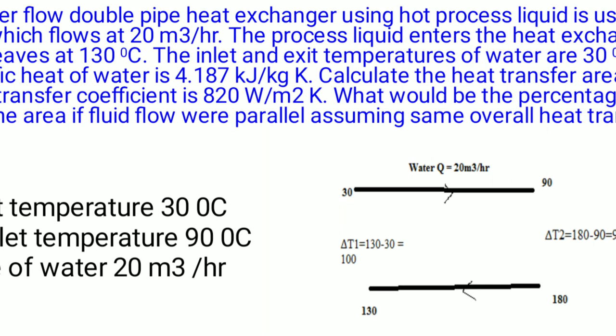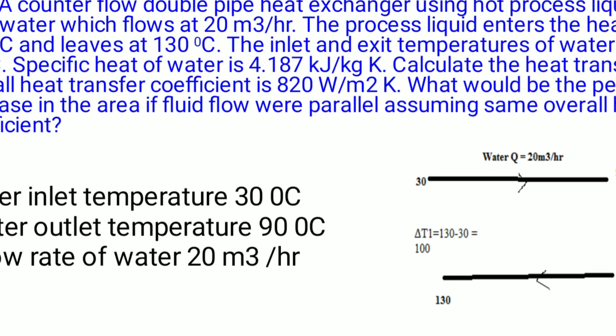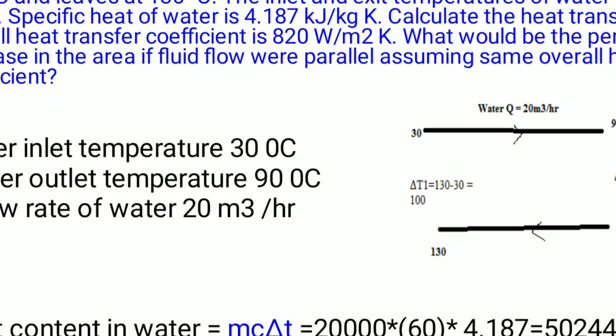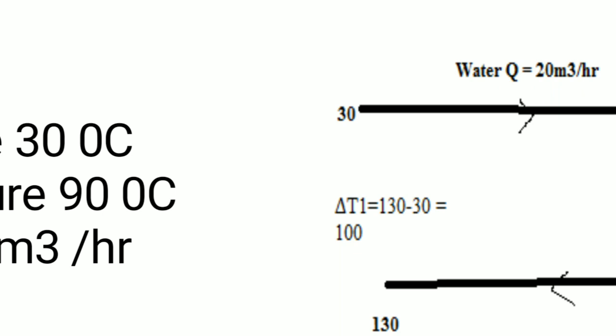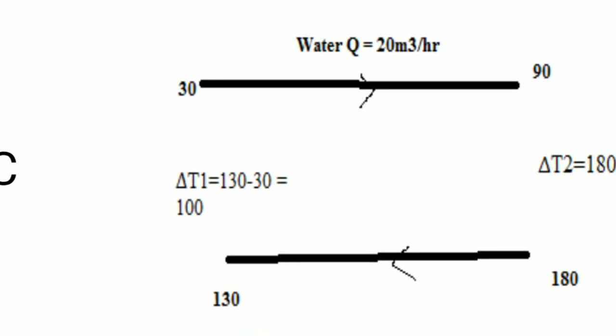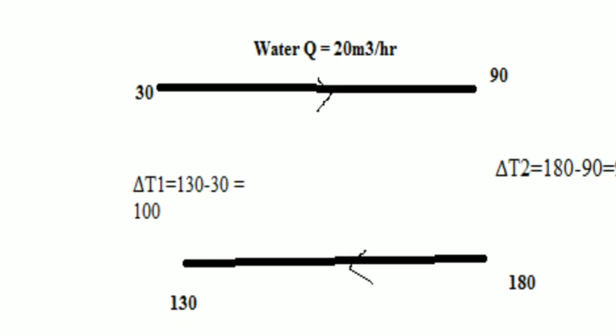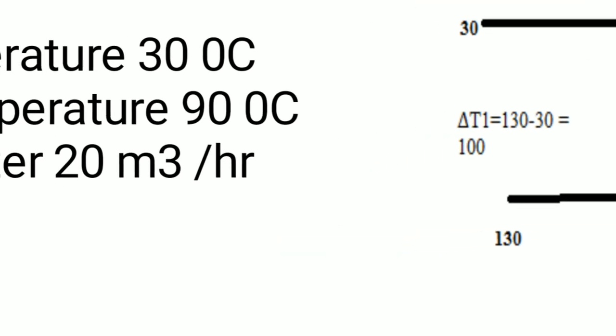In this counter-flow exchanger, the hot process liquid enters at 180°C and leaves at 130°C, while water enters at 30°C and leaves at 90°C. The fluids flow in opposite directions. Delta T1 = 130 − 30 = 100°C (hot liquid exit vs. water inlet) and delta T2 = 180 − 90 = 90°C (hot liquid inlet vs. water exit).